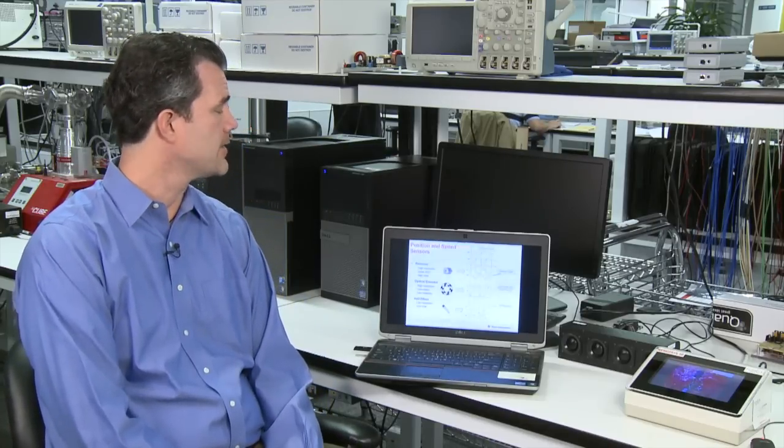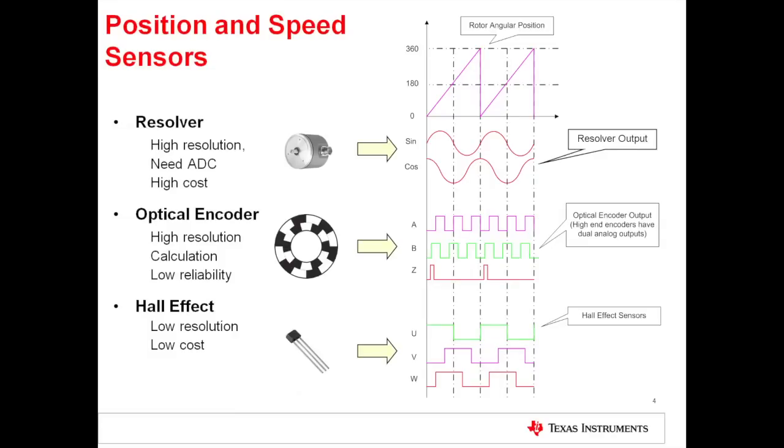Some of the more common sensors are resolvers, optical encoders, and hall effects. Resolvers are typically in military heavy industrial applications. They're fairly expensive, extremely high precision. Optical encoders are more popular but I would say hall effects for commutation are definitely the most popular at a lower cost. And again what these encoders do is they give you that rotor positional information so your system knows the position of the rotor and then it knows when to turn on those electromagnets.